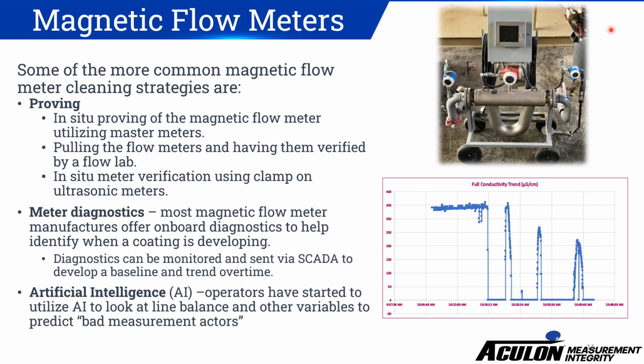Diagnostics are also utilized. Most magnetic flow meter manufacturers offer onboard diagnostics to help identify when coating is developing. These diagnostics can be monitored and sent via SCADA to develop a baseline and trend over time. I have an example of one manufacturer's use of conductivity to determine when a non-conductive fluid is present in the meter. If the conductivity drops significantly and stays at a low level, it's a very strong indicator that the meter has fouling and would need to be cleaned.